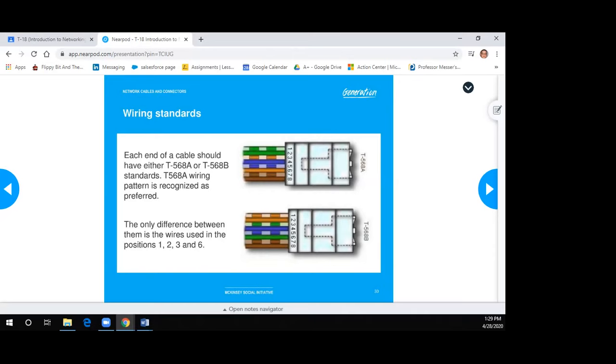Now the trick is, unfortunately, in the third one, you're going to go to orange. So the colors are green, orange, blue, brown. Problem is, whenever you get to the third one, he actually splits his legs open and lets blue in. So you have the white orange, now you have solid blue, white blue, and now you have solid orange. And you finish it off with the white brown, brown. It always finishes white brown, brown. The second one now starts with orange instead of green. You just flip-flop orange with green. That's the coloring of B.